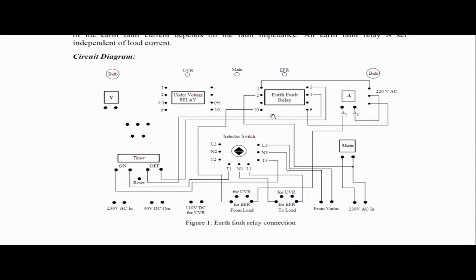For the earth fault relay, we just need to put the switch in the downward position, so that T1 is short circuited with T3, N1 is short circuited with N3, and similarly L1 is short circuited to the L3 terminals. In the same experimental table, we can experiment with two relays: one is the under voltage relay and the other is the earth fault relay. But for this particular experiment, the under voltage relay is not required. So these are the terminals which are left open.